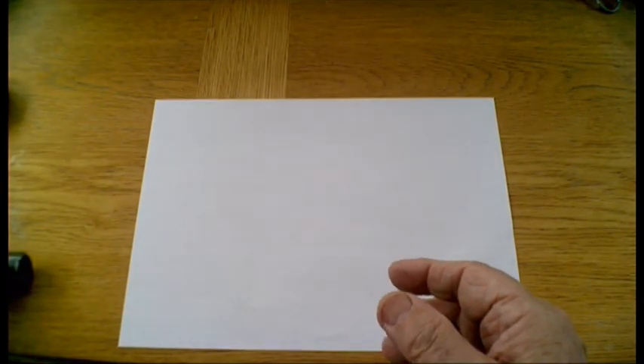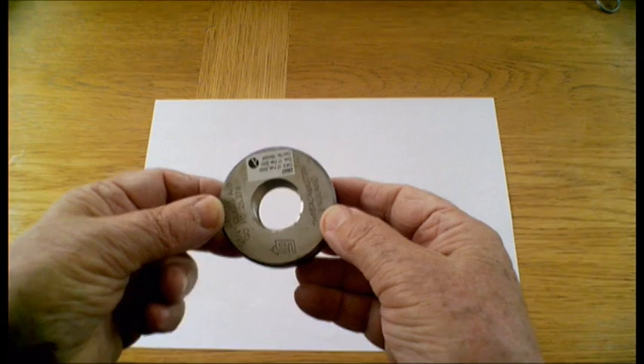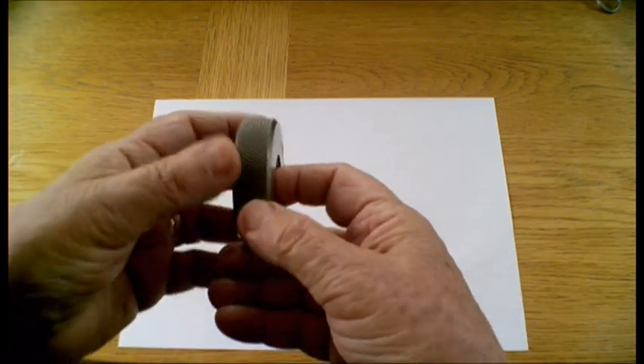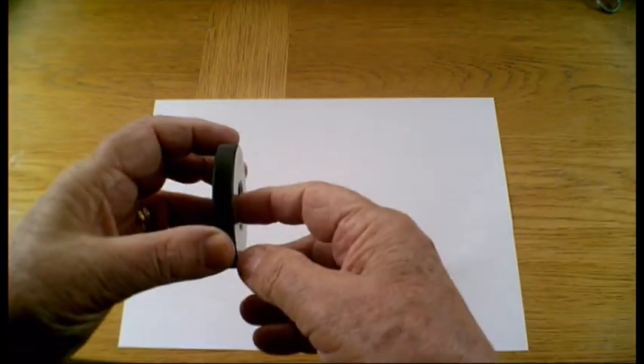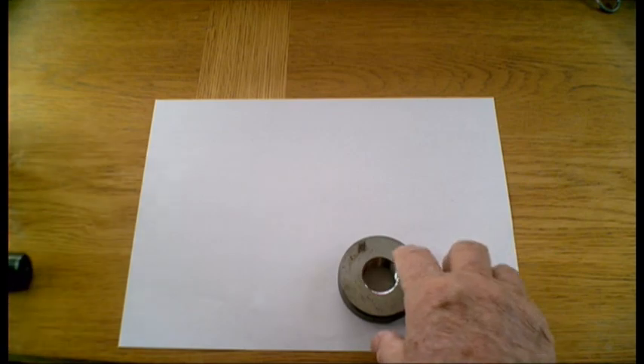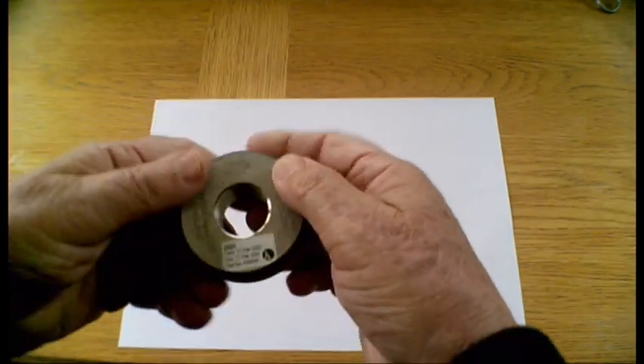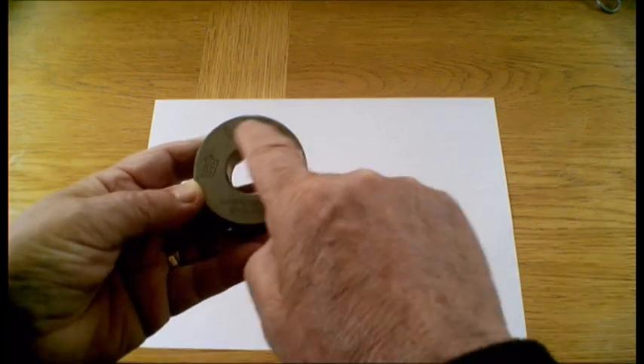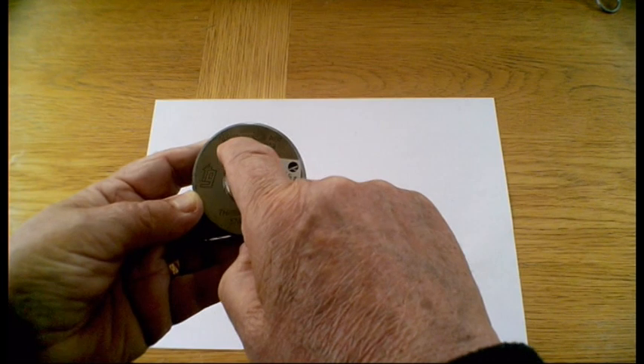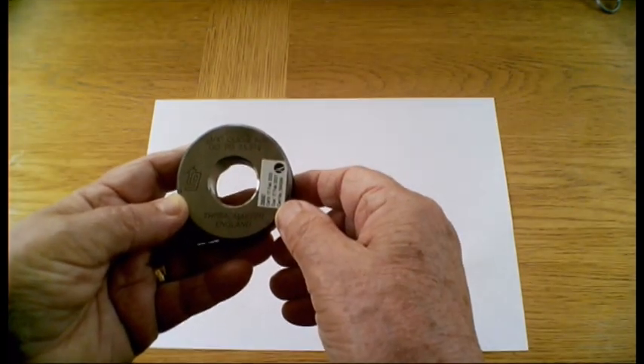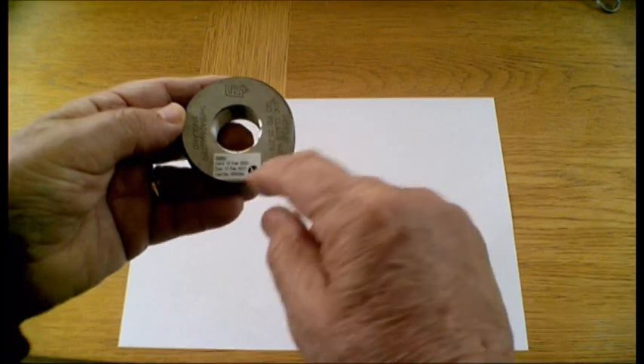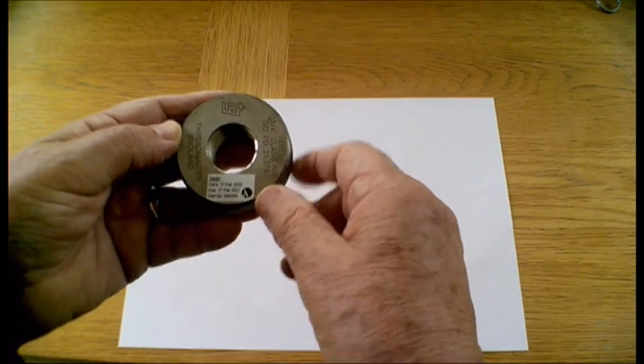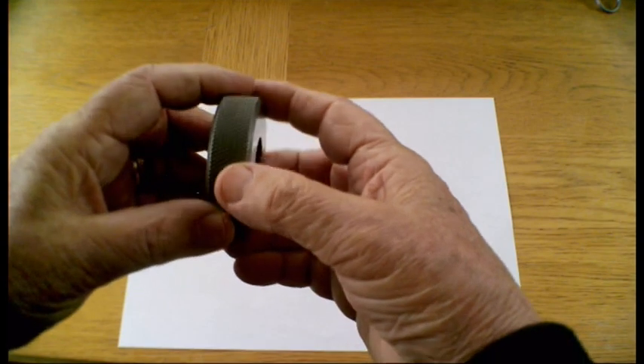The other type of gauges that we have are the ring gauges. These are in two types. There is a thick go ring gauge and a thinner no-go ring gauge. The go gauge has a front on it with all of the details etched into its surface. In this case it's a G3/4. It tells you it's the go, and here is the serial number at the top, 28567. The sticker on the side here tells you when the gauge was actually tested last by a UKAS accredited laboratory, and that is used on external threads because that is the female.